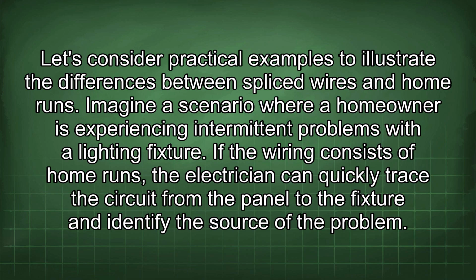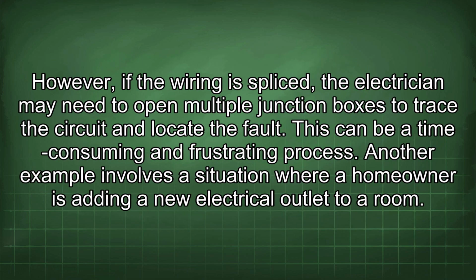Imagine a scenario where a homeowner is experiencing intermittent problems with a lighting fixture. If the wiring consists of home runs, the electrician can quickly trace the circuit from the panel to the fixture and identify the source of the problem. However, if the wiring is spliced, the electrician may need to open multiple junction boxes to trace the circuit and locate the fault. This can be a time-consuming and frustrating process.